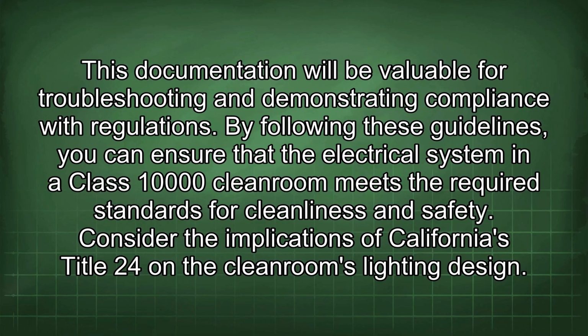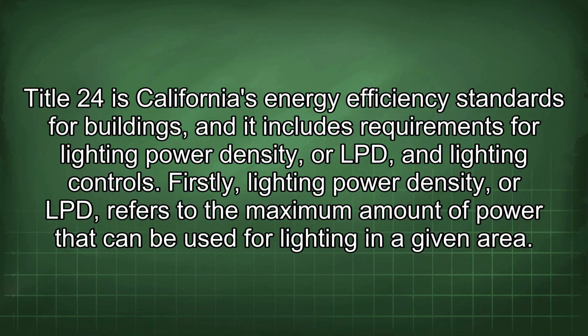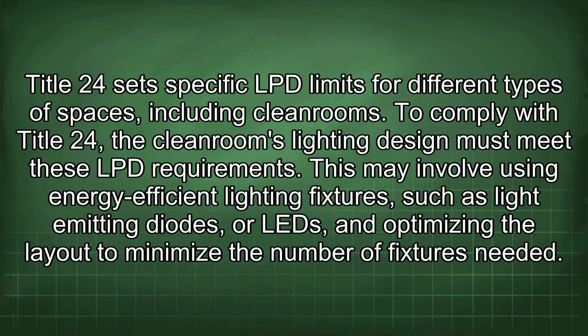for cleanliness and safety. Consider the implications of California's Title 24 on the cleanroom's lighting design. Title 24 is California's energy efficiency standards for buildings, and it includes requirements for lighting power density, or LPD, and lighting controls. Firstly, lighting power density, or LPD, refers to the maximum amount of power that can be used for lighting in a given area. Title 24 sets specific LPD limits for different types of spaces, including cleanrooms. To comply with Title 24, the cleanroom's lighting design must meet these LPD requirements.